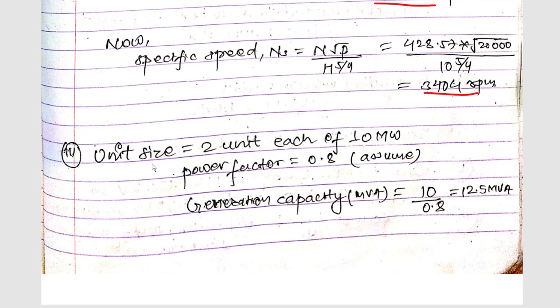The plant capacity is 20 megawatts, so we assume 2 units, each of 10 megawatts. Assuming power factor of 0.8, the generation capacity in MVA is 10/0.8 = 12.5 MVA. So 12.5 MVA generation capacity, each of 2 units.